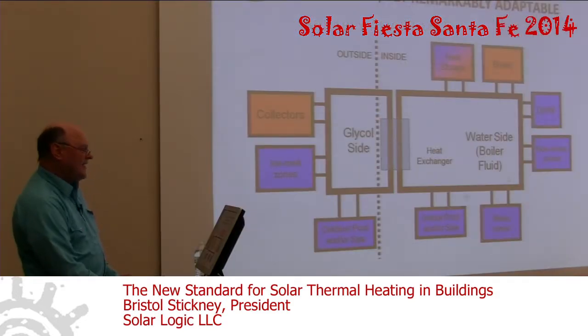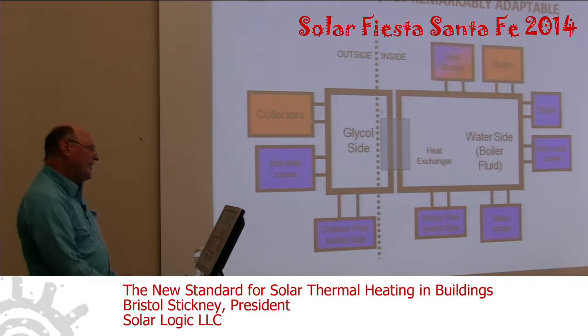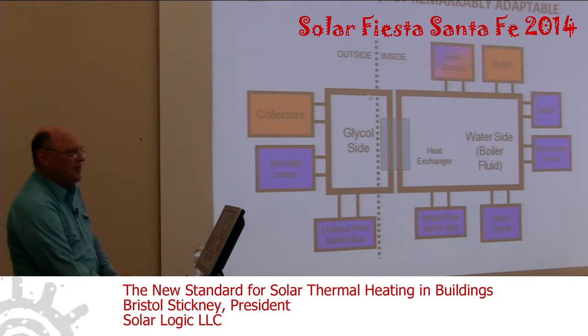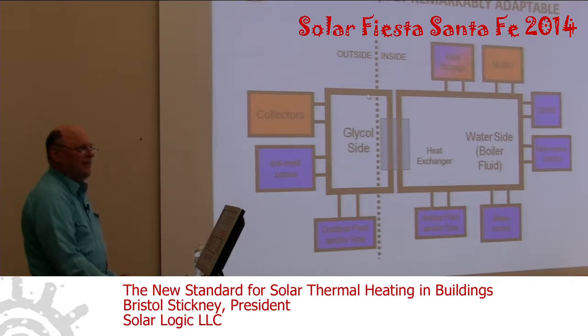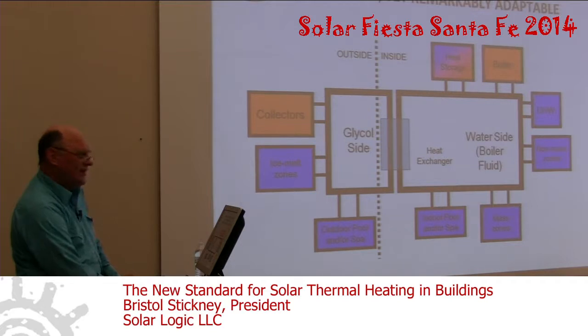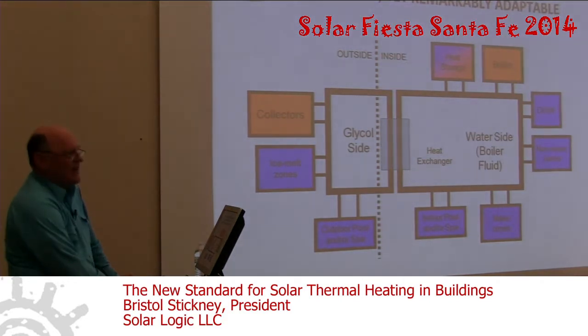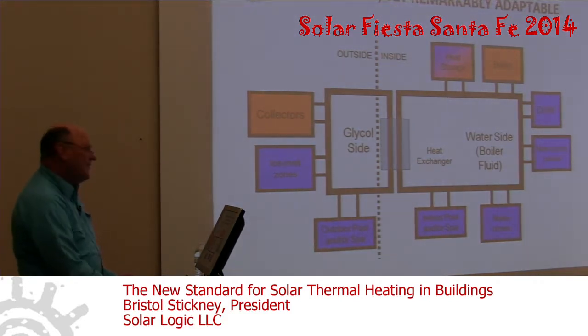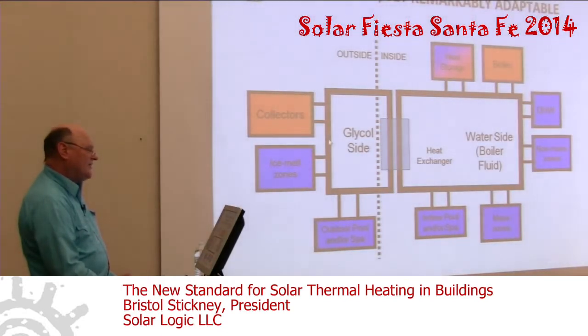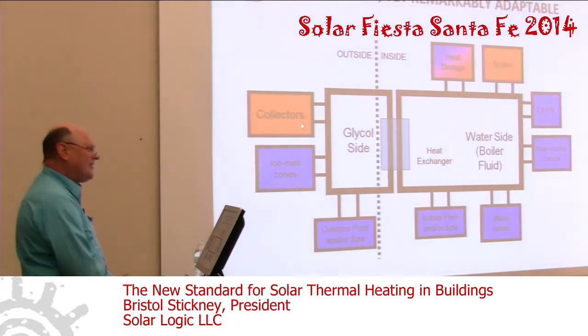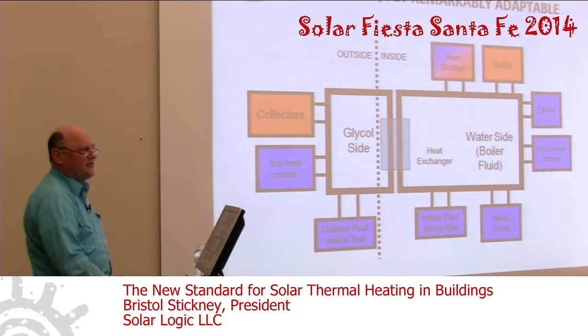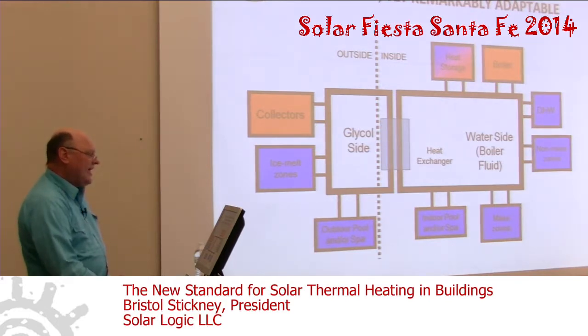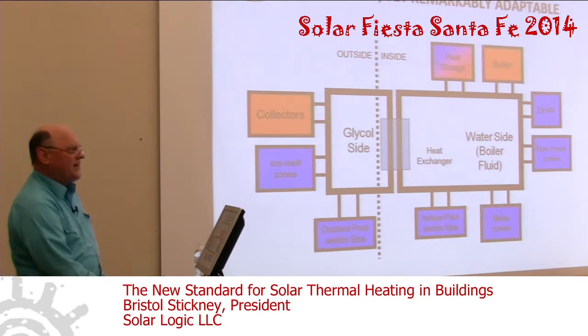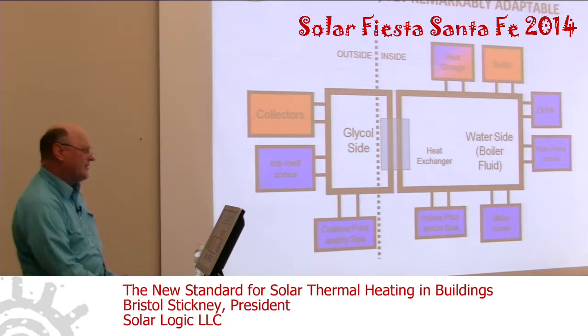That's the water that's heated by the boiler, typically in a normal boiler heating system. The way we adapted to this is we added a second loop out here that has plumbing that goes outdoors. And we put propylene glycol antifreeze in there, usually, although we can also use drain back collectors and use water with a drain back system if that's required. But our typical standard has glycol in the plumbing that runs outdoors. So the collectors are usually outdoors. The collectors will either be ground mounted near the house or be mounted on the roof. And since that is outdoors, that could be in danger of freezing, and that's why we run antifreeze in the plumbing outdoors.